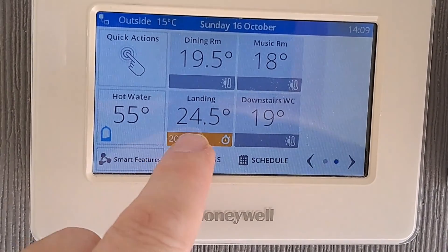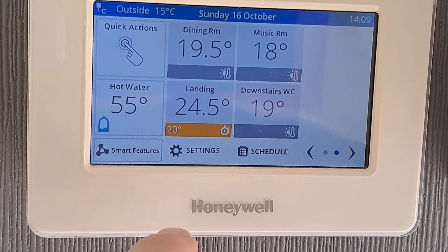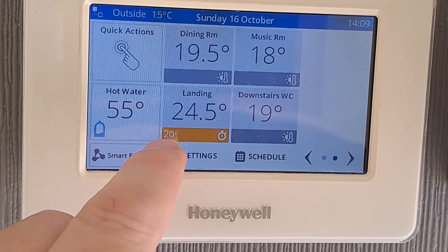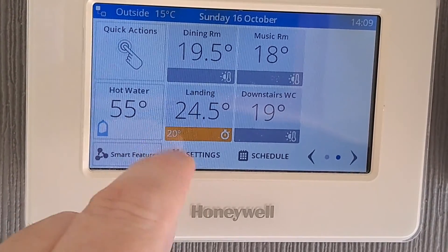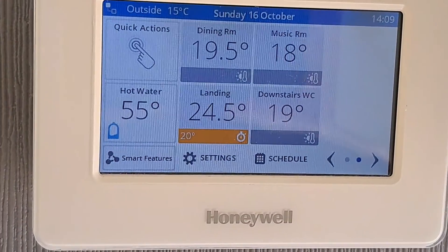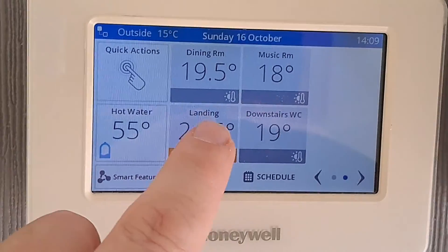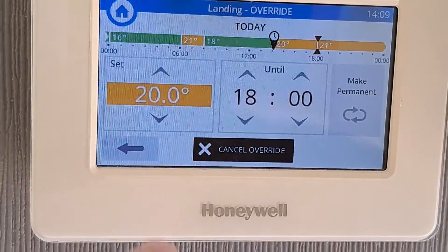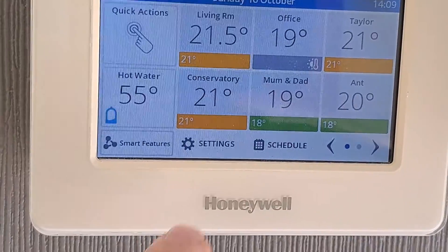...you can see the zone has now come back up on the panel, showing the current temperature of 24.5°. The little warning symbol has gone, and before it wasn't showing the temperature at all. We're not getting any errors now — if we click on it, the error arrow no longer comes up.